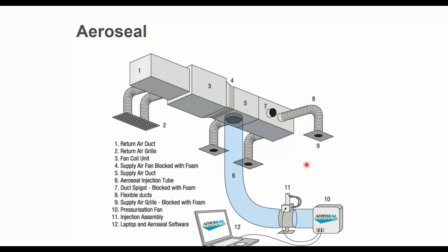It is very much like getting a cut on your hand, and this is so gross, I know, I get it. But you see the scab closing up over the course of the day from the outside inward, and it closes up. The same thing is going to happen here. The glue is going to build up on the outside of the crack, and then it's going to close up. The aeroseal process can effectively seal about a 5/8 inch gap. It could do something slightly larger than that, but it takes a long, long time, and it's not practical. But you've got little gaps and little cracks up to a 5/8, which is actually pretty big. 5/8 is way bigger than a duct leak you should have. It'll seal those gaps up.